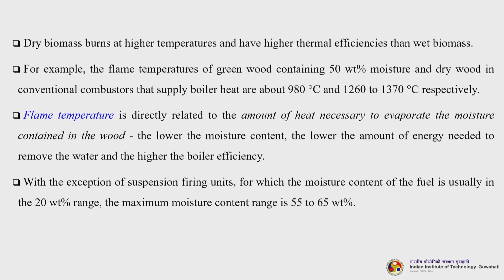Many of the large scale biomass combustion systems for producing heat, hot water or steam accept biomass fuels containing a relatively large amount of moisture and are operated without much apparent concern for the effects of moisture content of the fuel on the combustion process itself. One of the largest biomass fuel power plants equipped with travelling grates operates very well with wood chips containing an average of 58% moisture, although a few initial handling and storage problems caused by high moisture fuel supplies had to be solved.